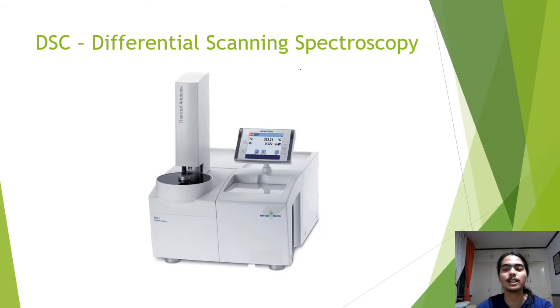DSC, differential scanning calorimetry. As material change states, the temperature difference will also change. For example, when a material melts, the temperature difference also changes rapidly. Melting points and other changes can also be determined, such as glass transitions and decomposition points.